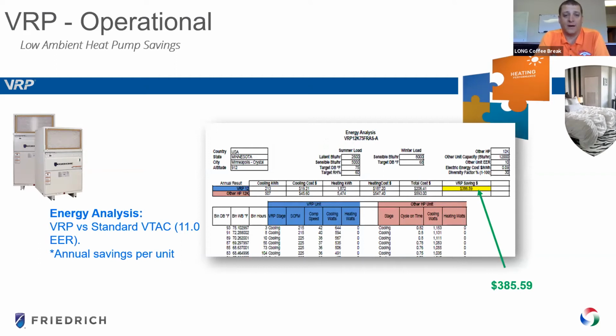And this is some bin data where they came up with an energy analysis saving. This is for Minneapolis, so it's a little colder than Colorado here, but also kind of gives you a good idea of the savings that's available in a cold weather climate where you're going to be heating quite a bit of the year. So in Minneapolis, they've found that the VRP operational savings based on their local energy costs were about $385 per year. So while the VRP does cost more upfront compared to your standard VTAC or PTAC, the savings ends up adding up pretty quickly for the owner.